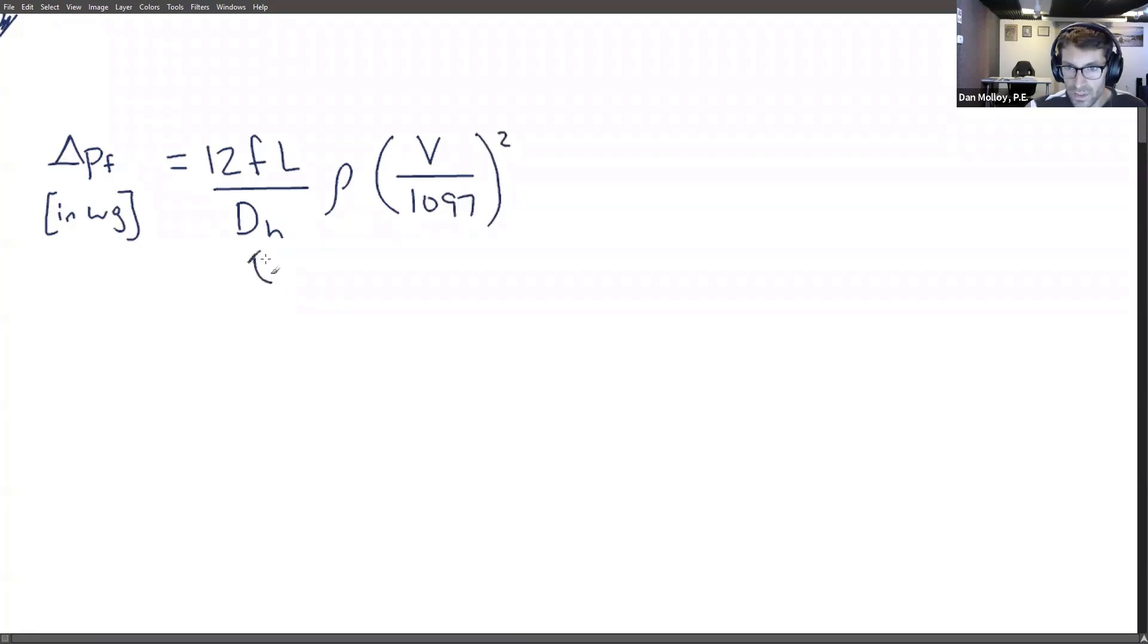And a couple of notes as we go into this: this is meant to go in in inches. This is meant to go in in feet per minute, feet per minute velocity. The density is meant to go in in pounds per cubic foot. And the friction factor is unitless and the length is meant to go in in feet.